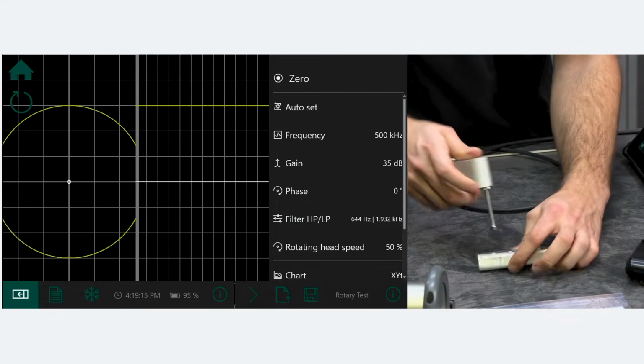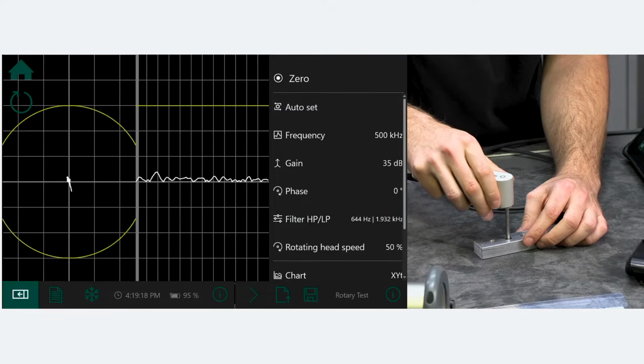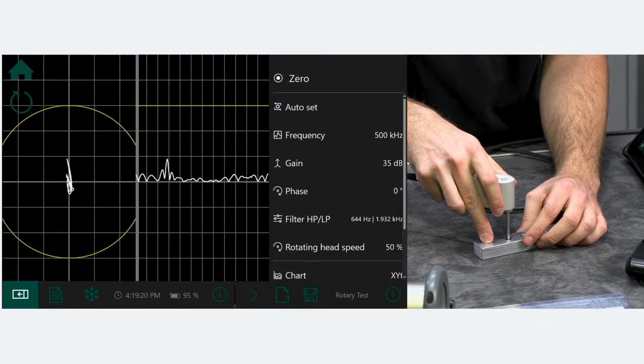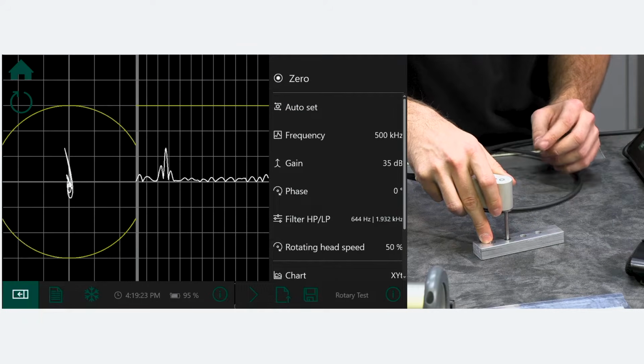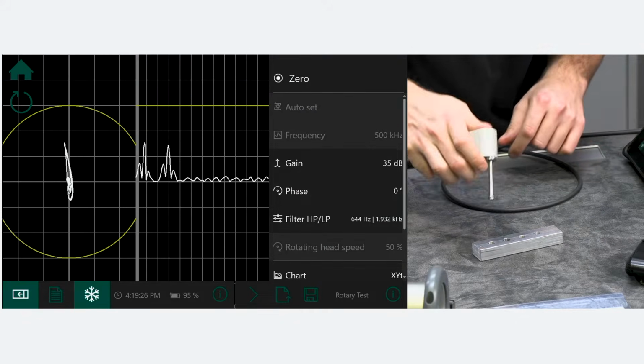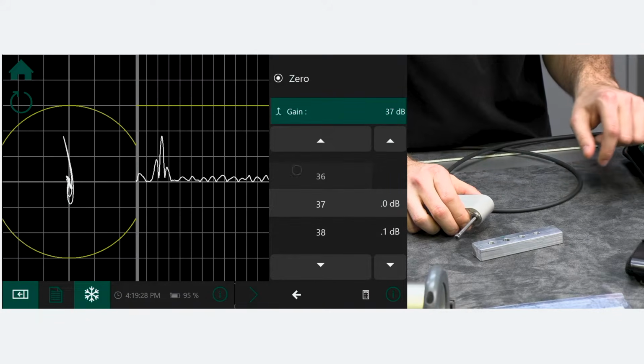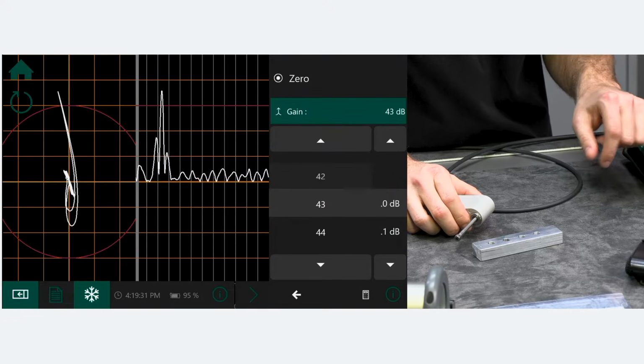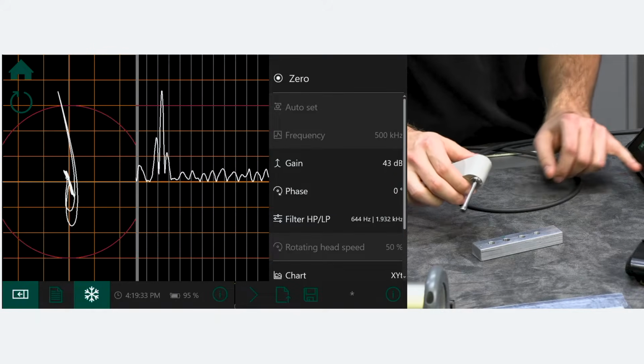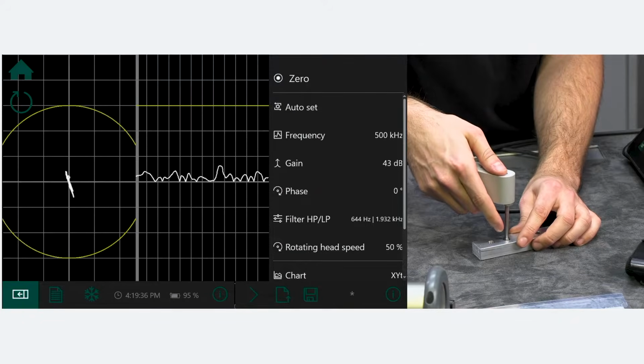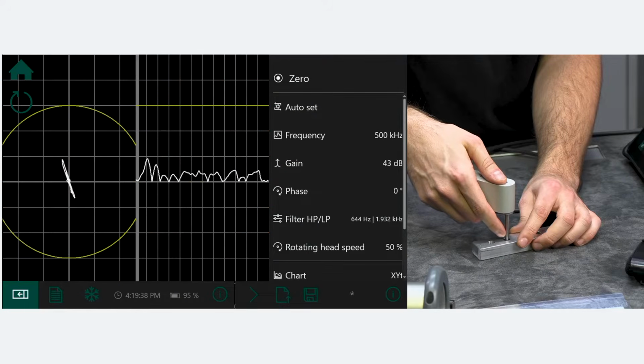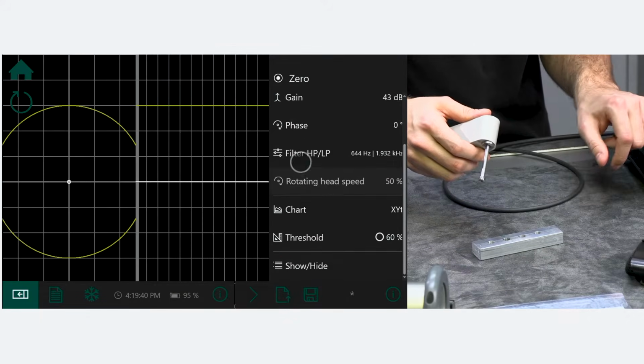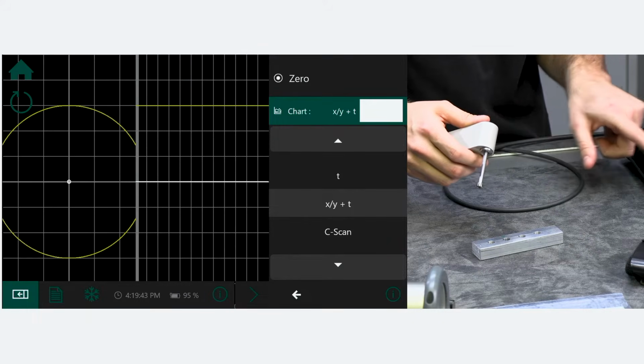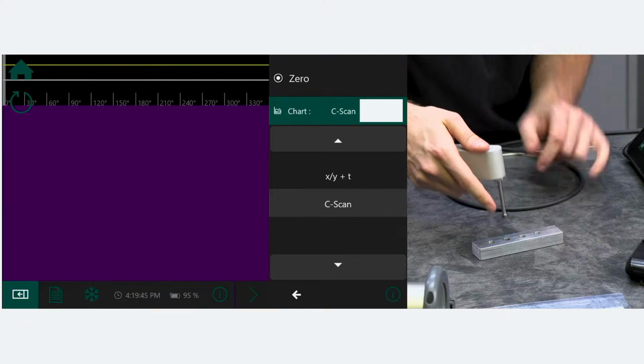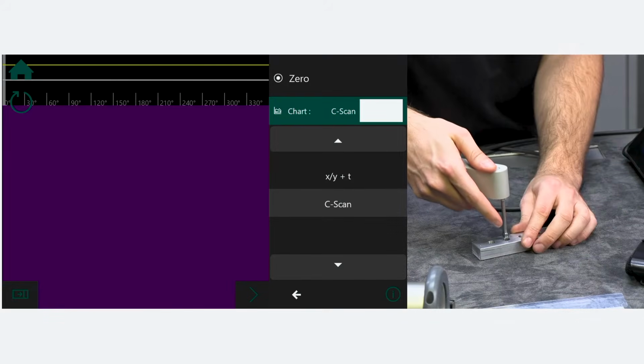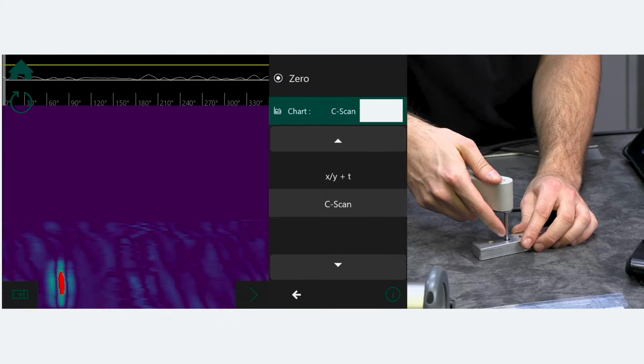So we scan the borehole. There is a crack, and I can freeze the signal and increase the gain until this crack reaches the threshold. Okay, and now I'm ready for scanning. Sure, this is the standard eddy current signal. And we can also go to chart, C-scan, and then we already have the C-scan. I will click this, and we can scan.